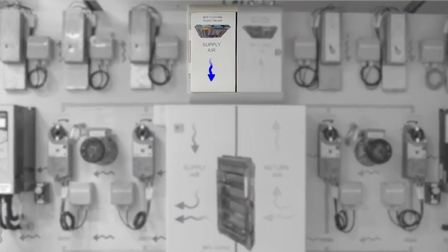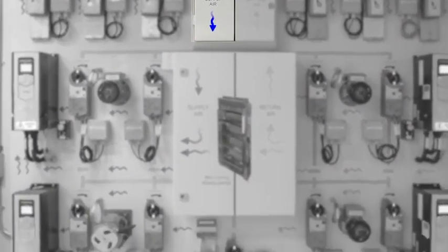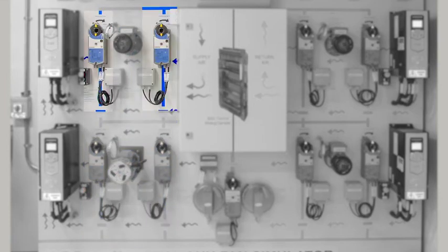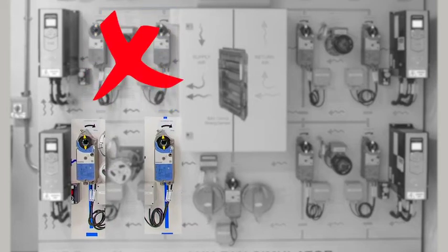The outside air inlet damper supplies fresh air to 2 active parallel systems, creating a fully redundant solution. Either parallel section can be isolated individually from the main common supply by means of 2 associated isolation dampers on the inlet and outlet side of each fan unit. Should one unit fail, the running standby increases speed to meet process demand.